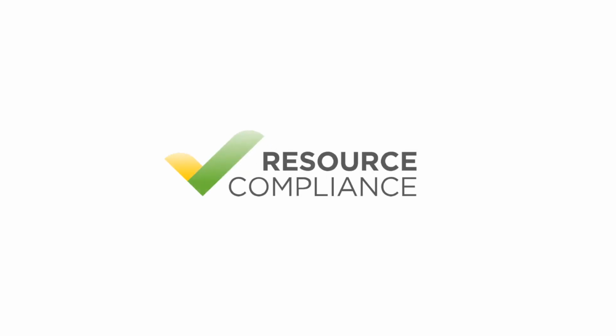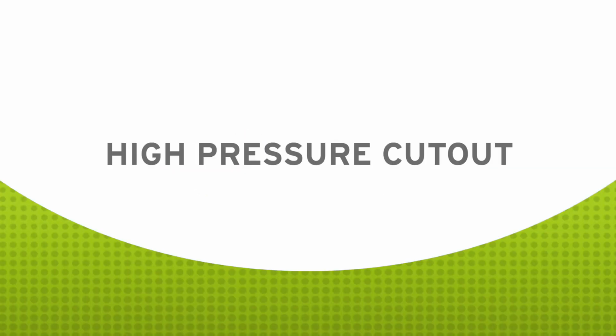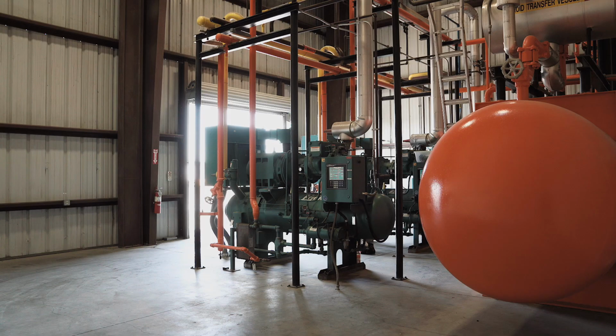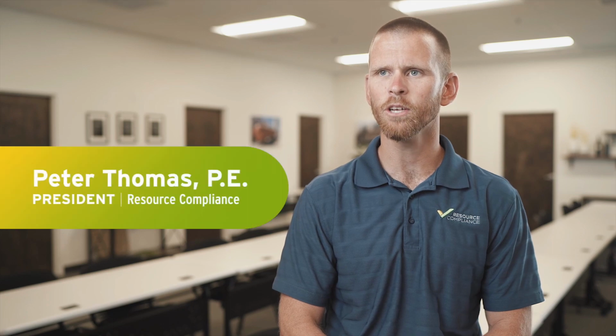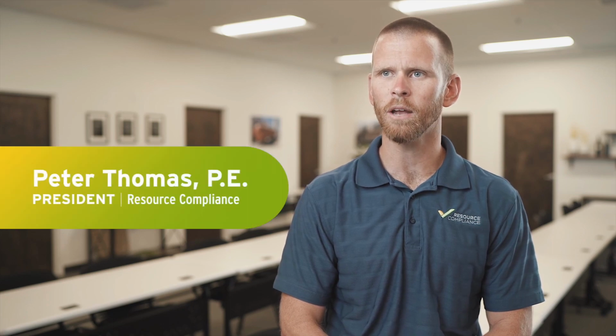This video provides more details on compressor cutouts and the process of performing the testing. A high discharge pressure cutout, or high pressure cutout as we've chosen to call it, is a safety device that must be installed on each compressor in an ammonia refrigeration system. Hi, I'm Peter Thomas, President and Senior Engineer at Resource Compliance.